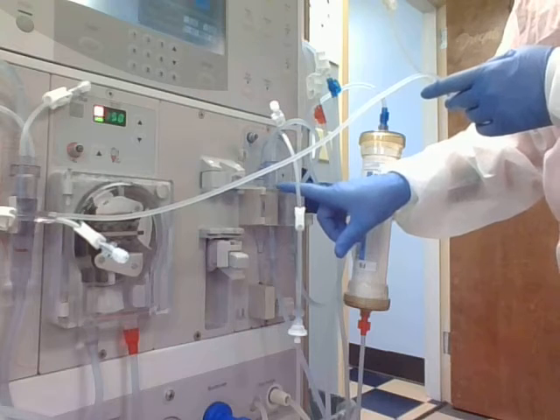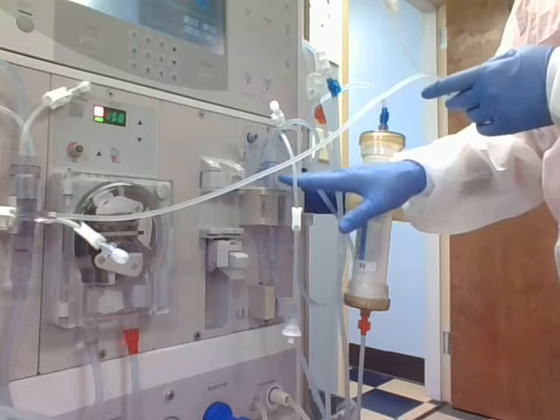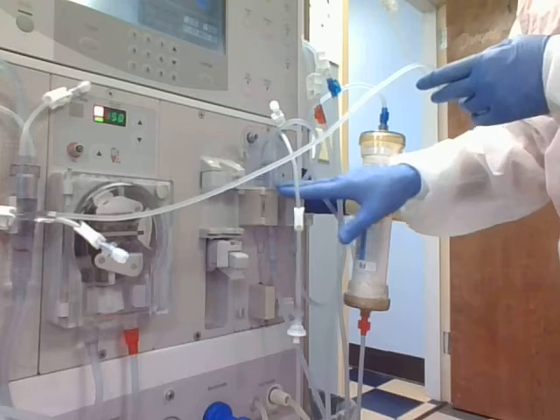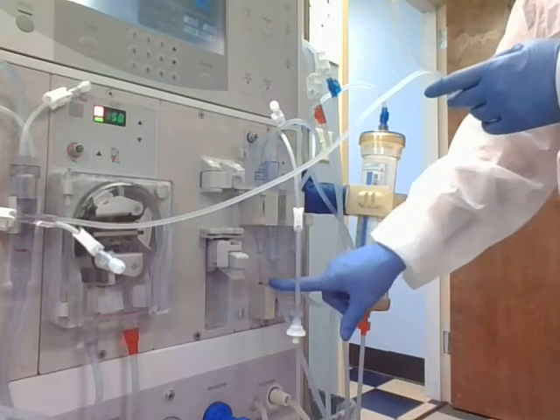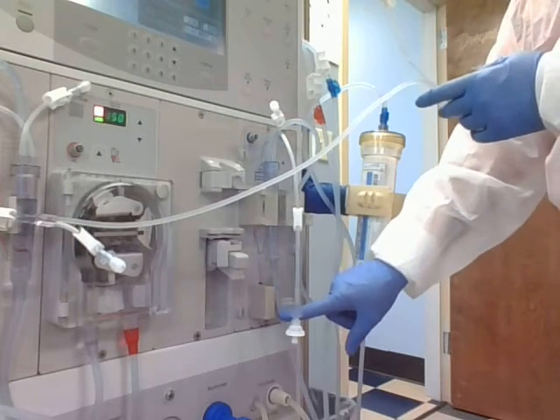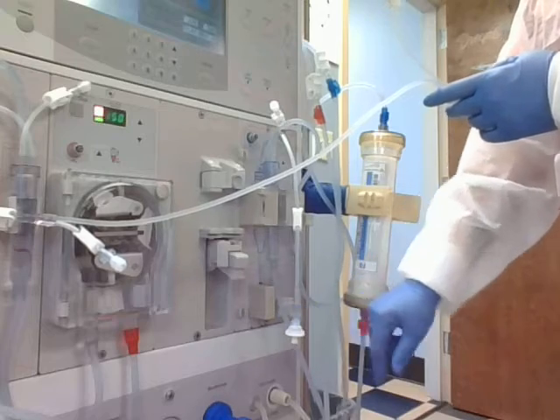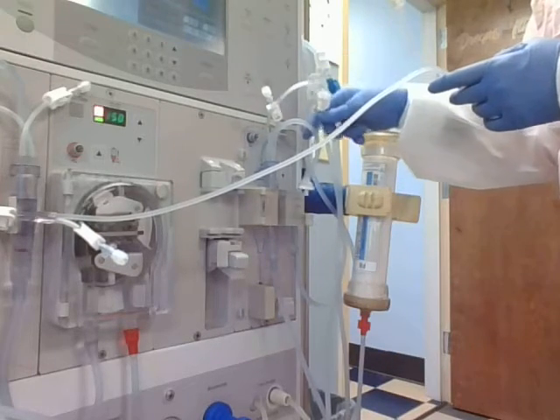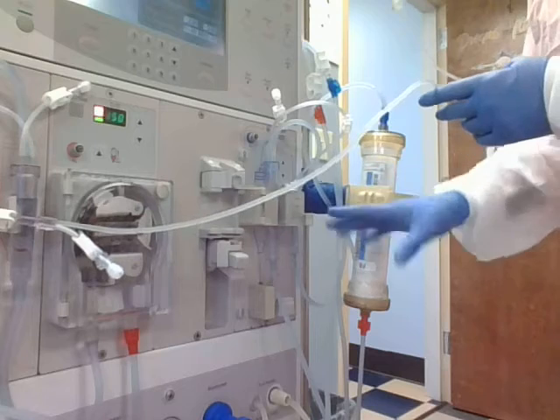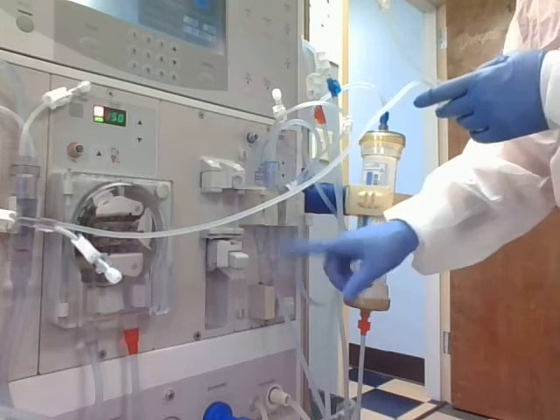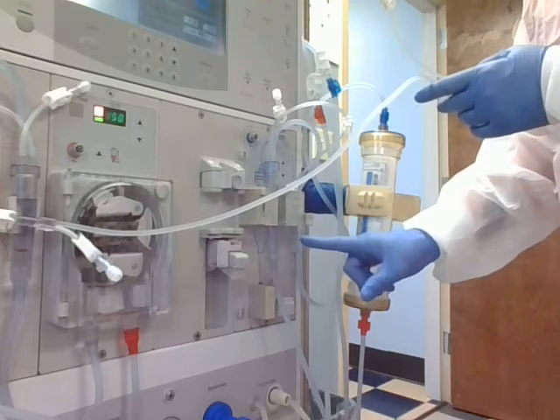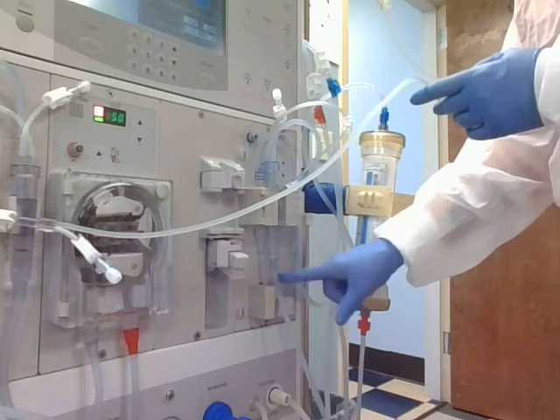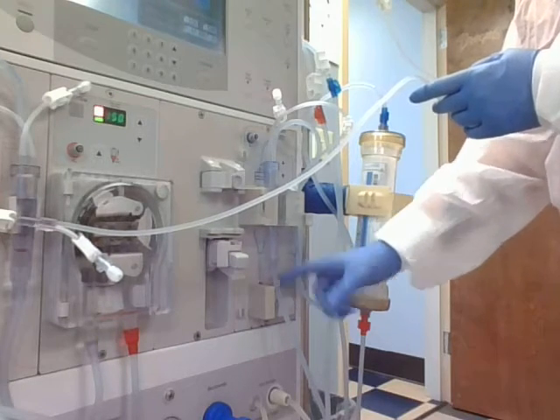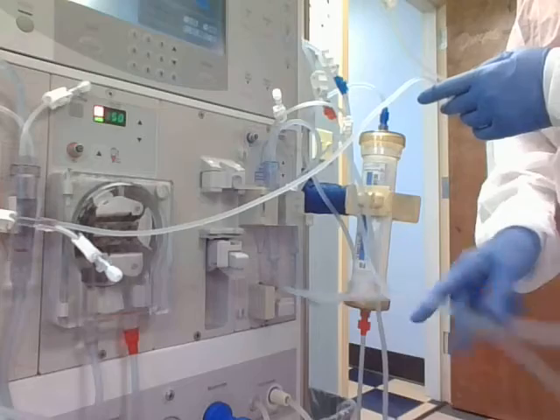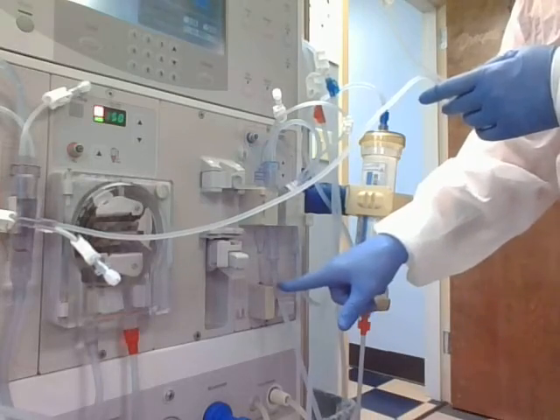The air foam detector, that's its purpose, which we're not going to get too deep in this video, but I need to arm my clamp, my venous line clamp. I need to make sure that it is armed so that as it is testing, one of the tests that the machine goes through is the venous line clamp to make sure that it works. So make sure before you start your test that you arm this.